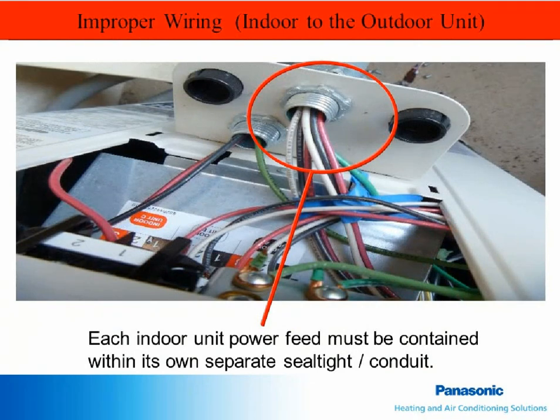In this picture, a multi-zone unit has a separate conduit for the power supply, but the 2 indoor units share a conduit for the interconnecting wires. Each of the interconnecting wires should have its own conduit to keep noise or induced voltage from causing communication and controls issues. Stranded wire should also be used.